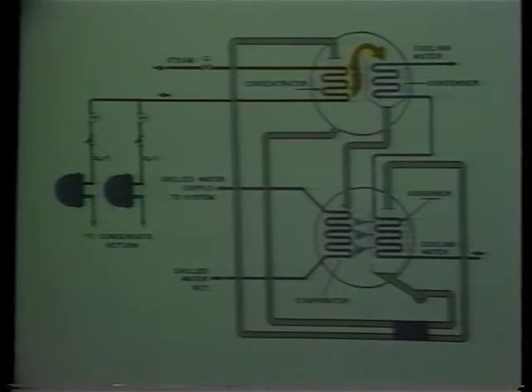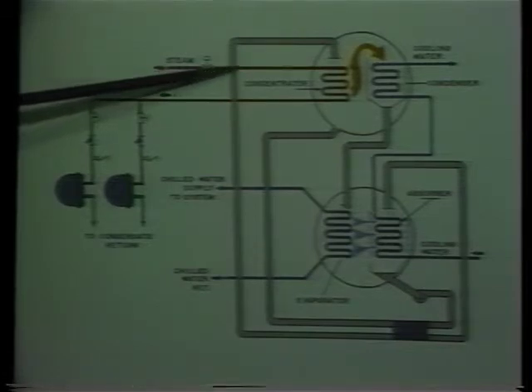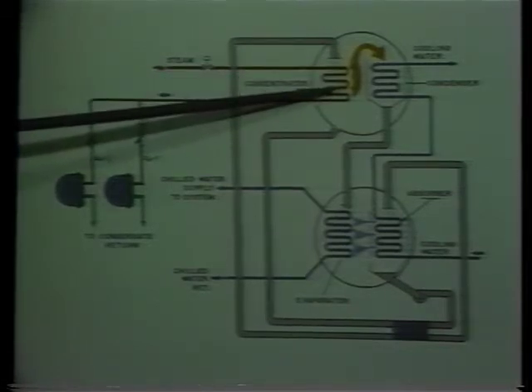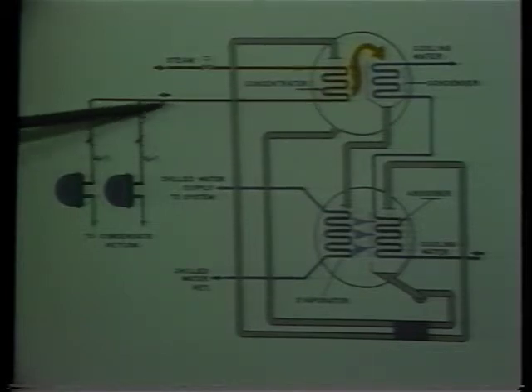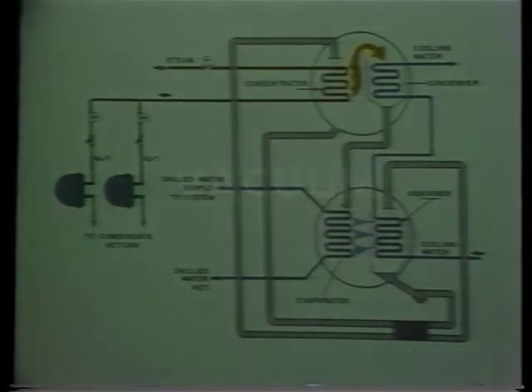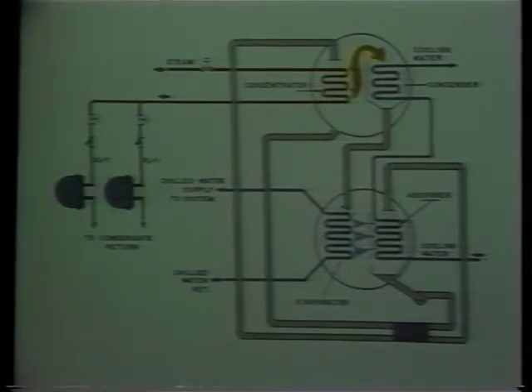During the operation of the chiller, the cooling load may be reduced, causing the steam control valve to modulate. Steam pressure to the concentrator section of the chiller decreases, possibly to the point where collapsing steam in the coils produces a vacuum at the trap. Then, the vacuum breaker will open, breaking the vacuum by admitting air. With the vacuum broken, condensate will flow if a drip leg of sufficient height has been provided. Keeping the concentrator free of condensate allows the system to retain its controllability and prevents freeze-ups. In addition, avoiding partial flooding of the coils eliminates the possibility of damage from water hammer or corrosion.